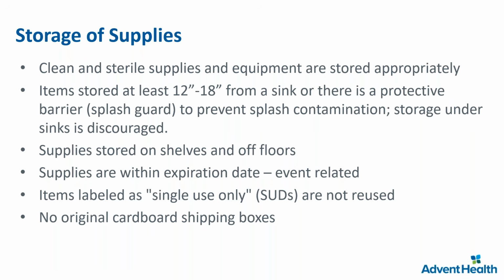When I say event related, every facility follows AORN, the Association of periOperative Registered Nurses, and also the AAMI standards. If you have a supply that went through the process of sterilization, in the past we used to say that if the package was paper, it would last 30 days, and other kinds of material would last another amount of days. But now we have a process that is called event related. If you open it and don't use it, it has lost sterility. So if the item can be sterilized again, it has to be sterilized. If the item was a disposable item, you need to discard it. Sometimes items don't have an expiration, meaning that if you open it and don't use it, you have to discard it.